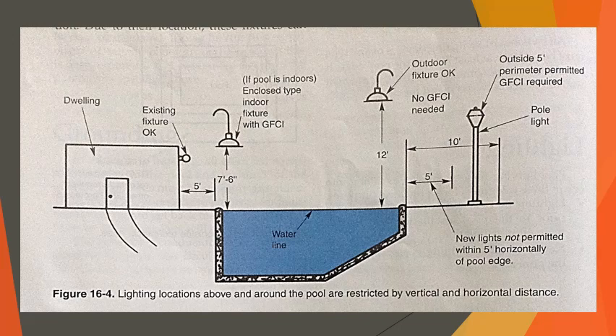The new lighting fixtures may be installed not less than 5 foot horizontally from the pool edge and will require GFCI protection. Lights may also be installed above the pool and should be no less than 12 foot above the water line for outdoor pools, or no less than 7 foot 6 inches above the water line for indoor pools.